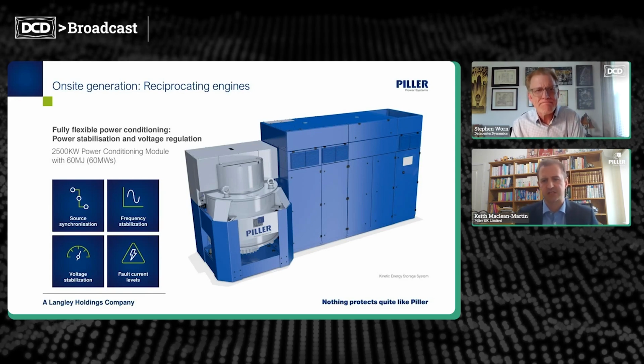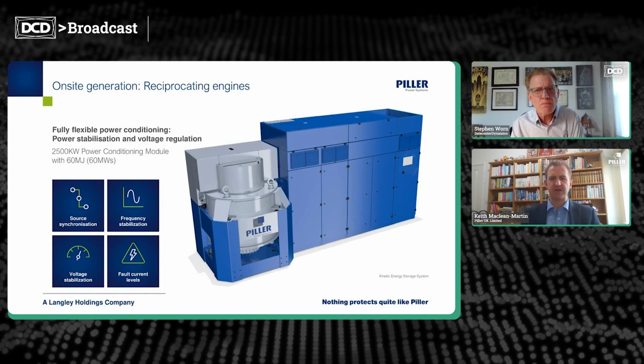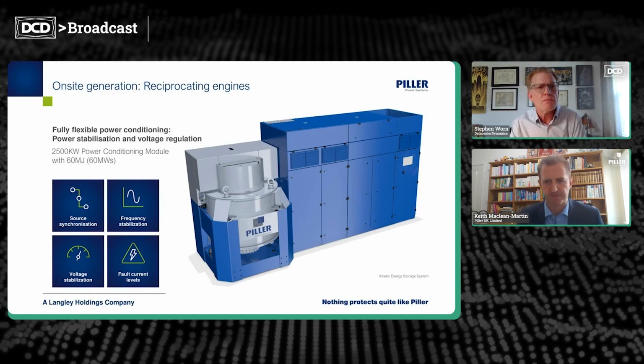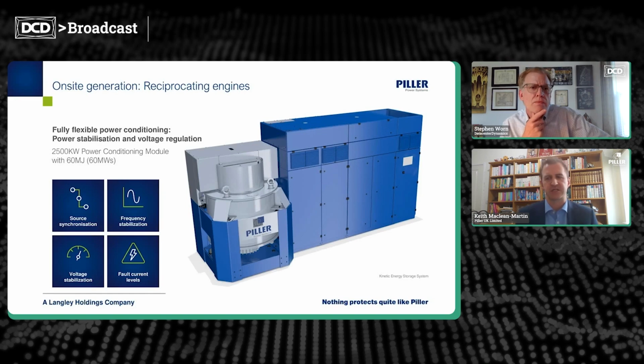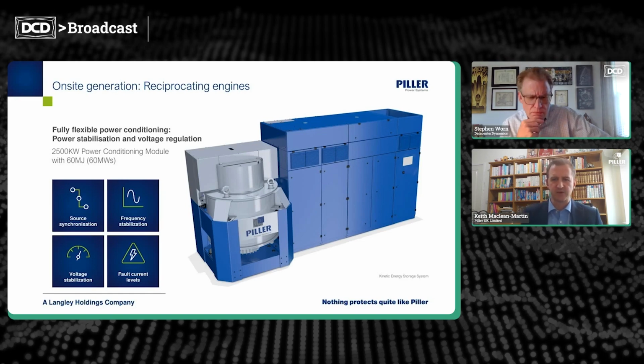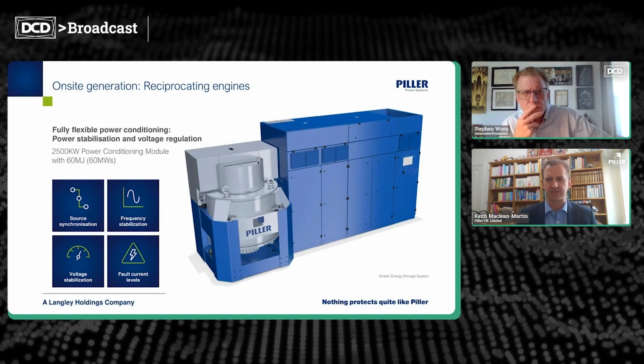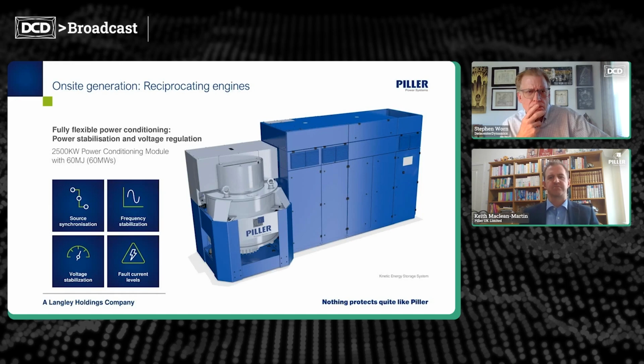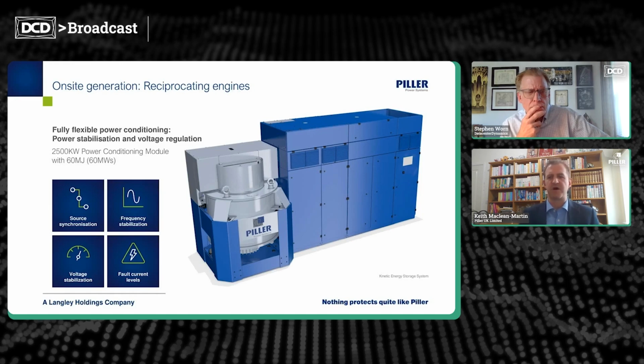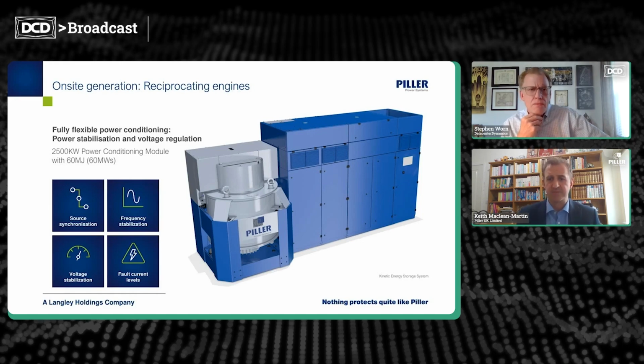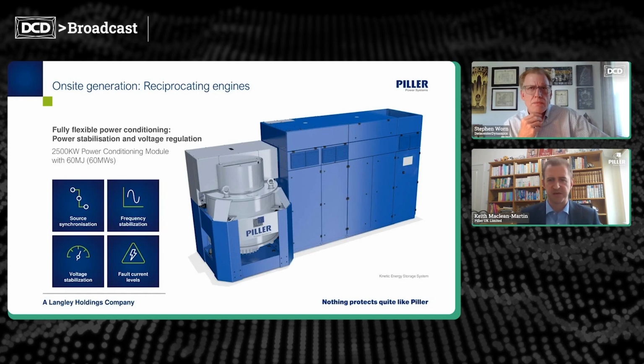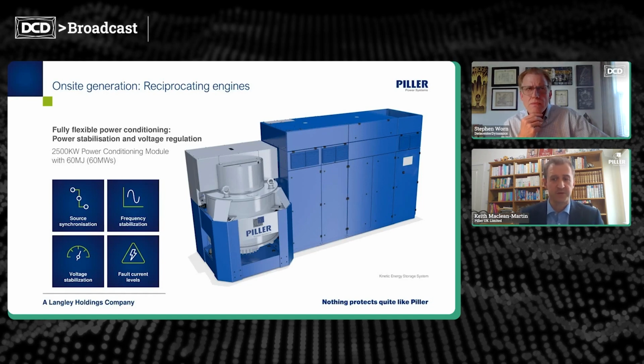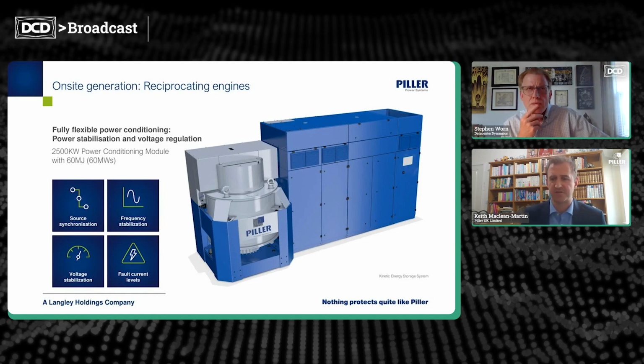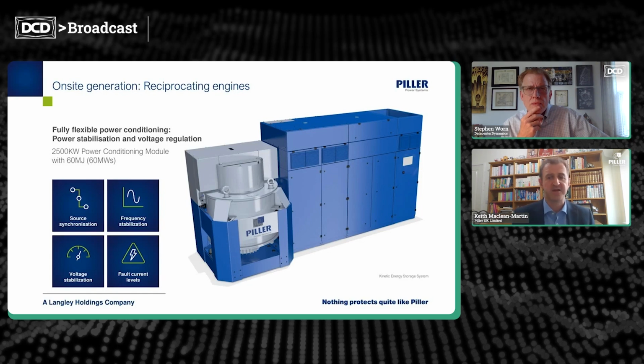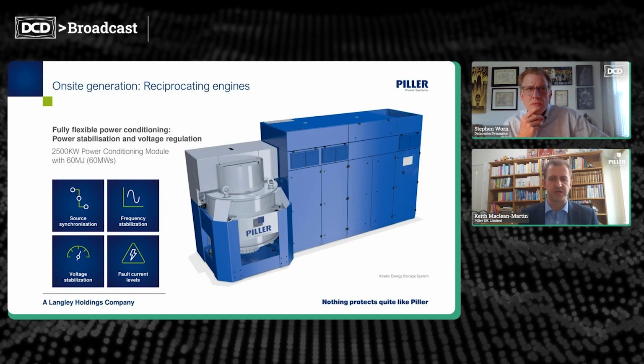Gas gensets and renewable energy sources typically have very slow responses to load demand changes. So frequency stabilization is achieved here with a regulated source and sink of active power compensation for rapid changes in balance between the supply and demand of this microgrid network, delivering a stable frequency into that space. Voltage compensation is also achieved for dynamic shifts in reactive power demand that could otherwise cause a significant voltage sag or surge on the microgrid.